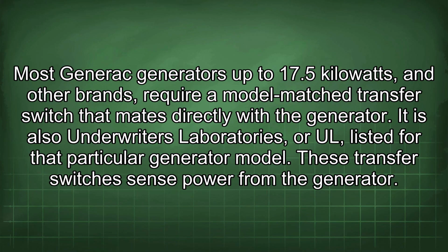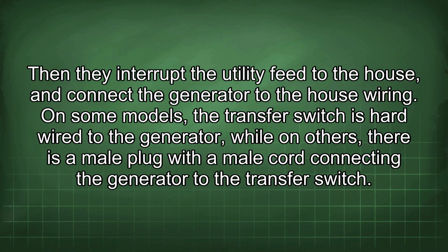Most Generac generators up to 17.5 kilowatts and other brands require a model-matched transfer switch that mates directly with the generator. It is also Underwriters Laboratories, or UL, listed for that particular generator model. These transfer switches sense power from the generator. Then they interrupt the utility feed to the house and connect the generator to the house wiring.